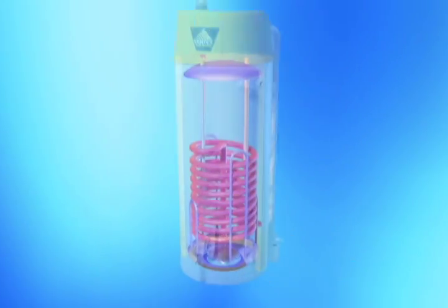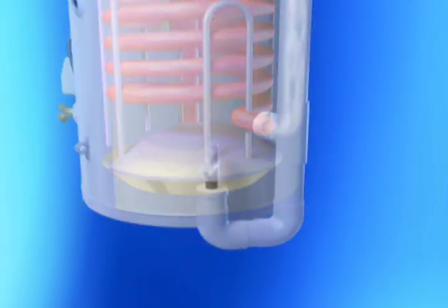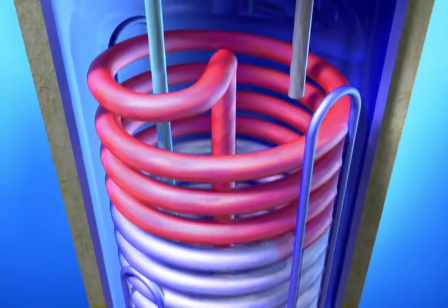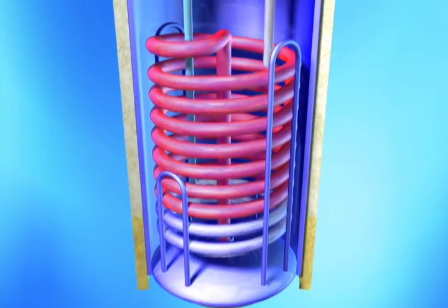From the heat exchanger outlet at the bottom of the unit, exhaust gases are drawn into the blower and vented out of the home through the power vent system. These gases leave Vertex much cooler than those leaving the standard design because so much more energy has been used to heat water.